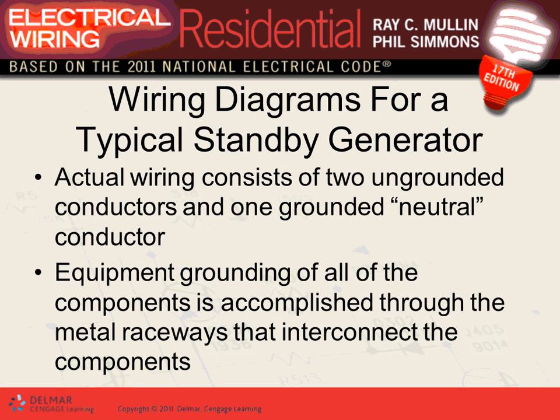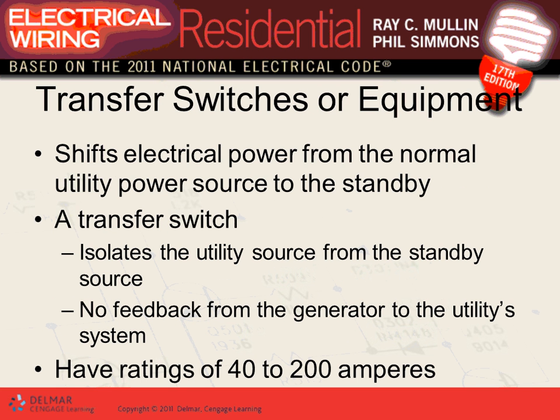Diagram for a typical generator, actual wiring consists of two ungrounded conductors and equipment grounding of all the components. So you can see, guys, when they wire it, you have to have two hots and a neutral coming out of the generator. A control wire has to be coming out of the generator in two different conduits. And an equipment grounding conductor, you have to bring an equipment grounding conductor or supply side bonding jumper, they call it, guys. If your conduit is EMT, then you're done. Or any type of metallic, the equipment grounding conductor will be done.